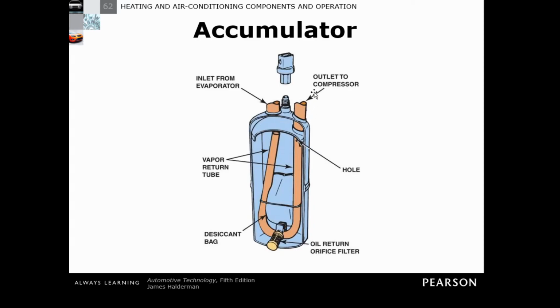Okay? So what actually happens is that the Freon itself has to boil, so it has to be a gas, because our liquid Freon is probably going to be floating around in here somewhere. So it has to become a gas until it can get high enough to actually go through this tube. And then it's able to be pushed out or sucked out to the compressor. Okay? So basically, because we have that tube up here, we ensure we're only getting gas to the compressor and no liquid.